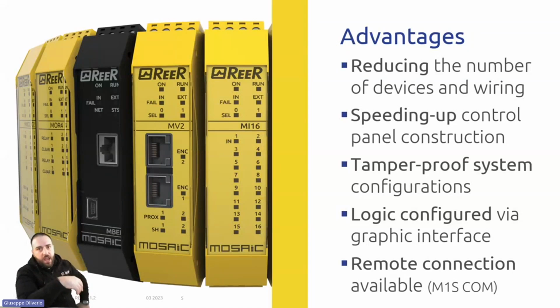We will see today, and we will see also during the technical training about the software and the PLC communication with the new controller. The system is a tamper-proof system. This means that you will have different levels of password. Different levels of password allow you to do different things, like only monitoring, downloading the software, or making some changes in the MSD software. And the MSD is the software, the Mosaic Safety Designer, that allows us to do every configuration.